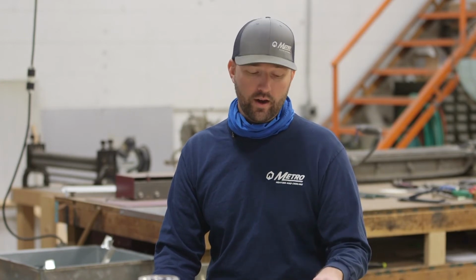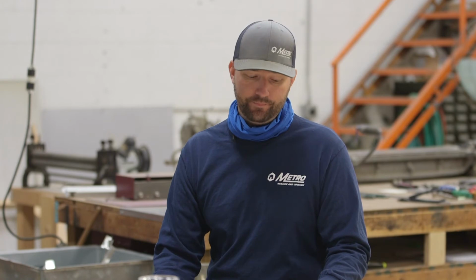So for that 16 by 8 ductwork, the max airflow I would feel comfortable with going through there would be 700 CFM. Each of those 6-inch pipes will be at 110 CFM, all equaling 1,030 CFM. So she has enough volume of ductwork to be pushing 1,030 CFM.